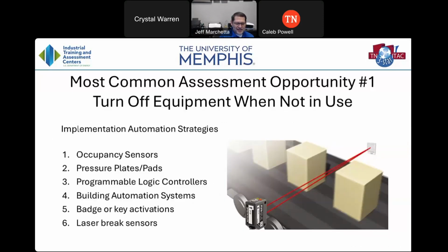Again, implementation strategies. I've talked about occupancy sensors for lighting, but for other things—if you're operating a production line and relying on the operator to turn equipment off for their lunch break, there are ways to handle that. You can use pressure plates, or badge and key activations that require an action to operate the equipment, so if they're not in the location, they don't have the badge there for the equipment to be on. We can also integrate things into the building automation systems if they have those.